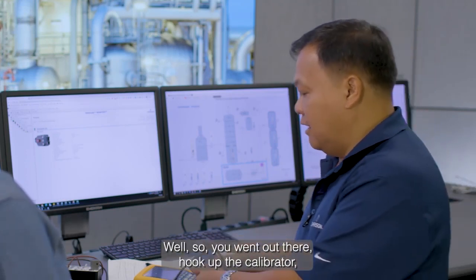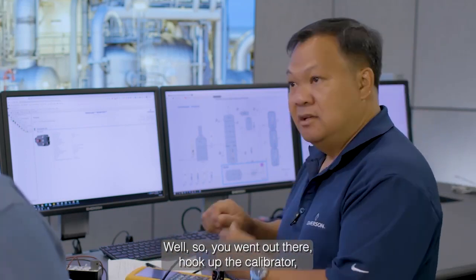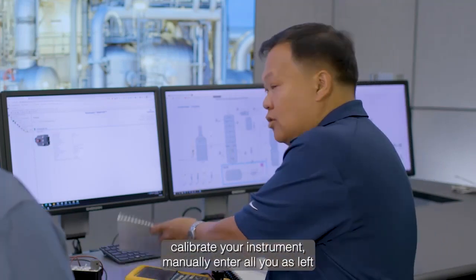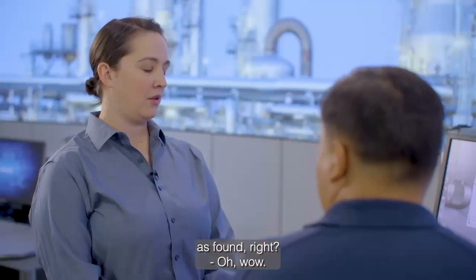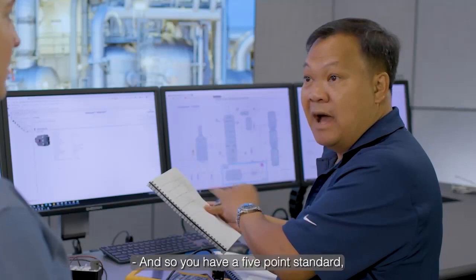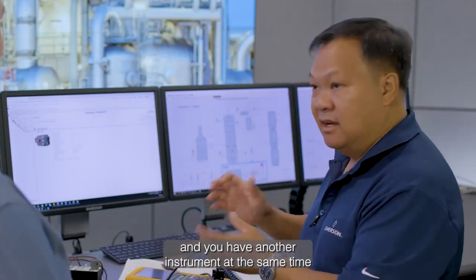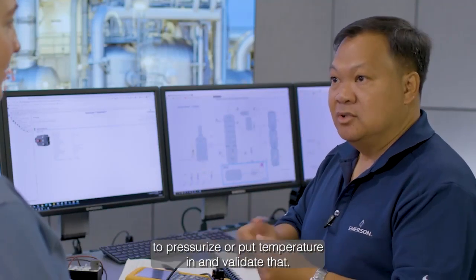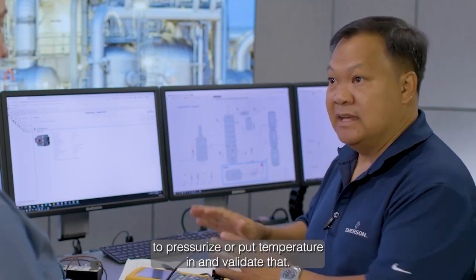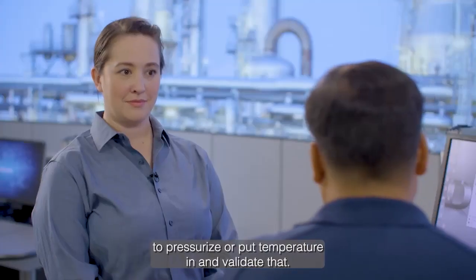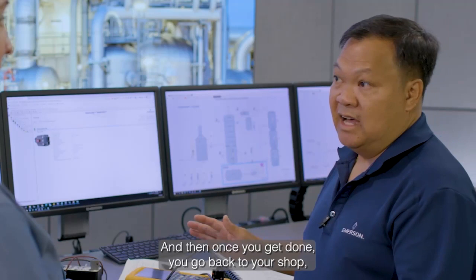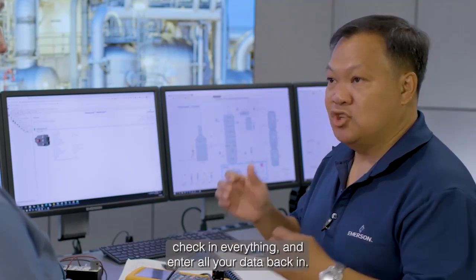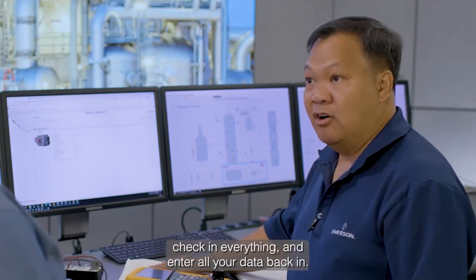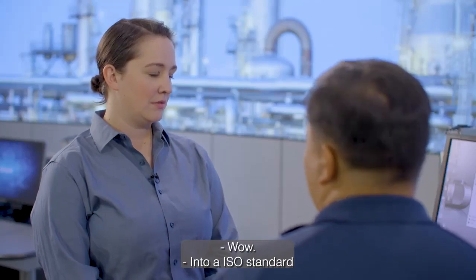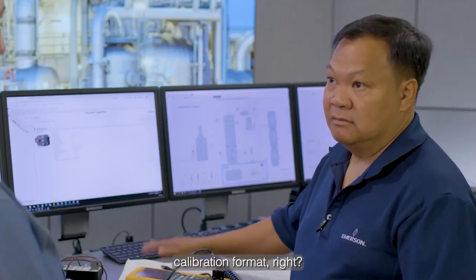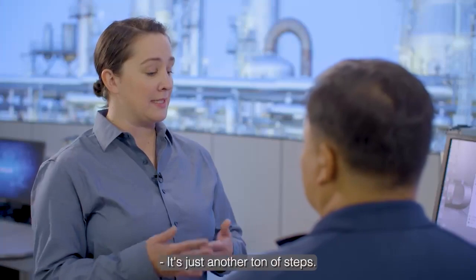Well, so you went out there, hook up your calibrator, calibrate your instrument, manually enter all your as left, as found, right? Wow. And so you have a 5-point standard, and you have another instrument at the same time to pressurize or put temperature in and validate that. And then once you get done, you go back to your shop, checking everything, and enter all your data back in into an ISO standard calibration format, right? It's just another ton of steps.